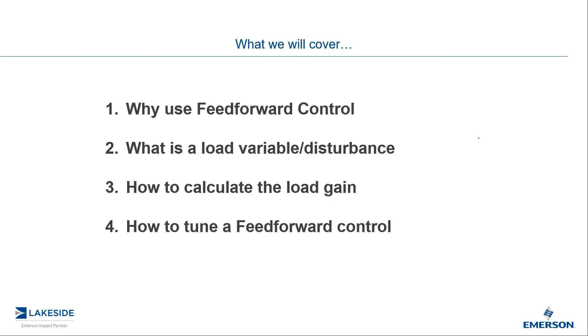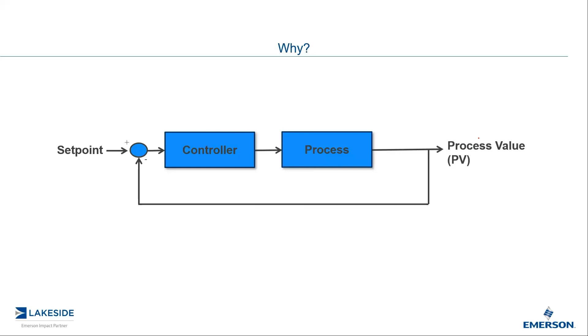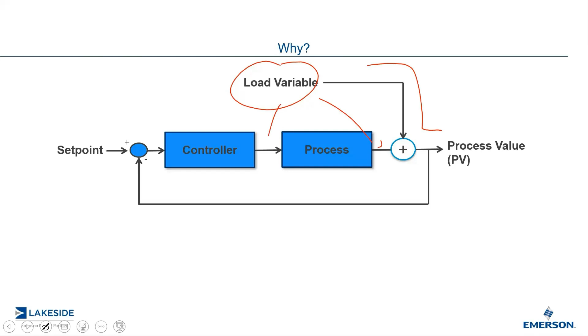So why? Let's say I have my controller with a set point going through my PID controller, which controls my process. I measure that process and it comes back - that's my standard PID loop. However, I notice there's this other load variable, and every time it changes, it affects the process. So if I can understand the relationship between here and here, maybe I could do something to offset that load disturbance.